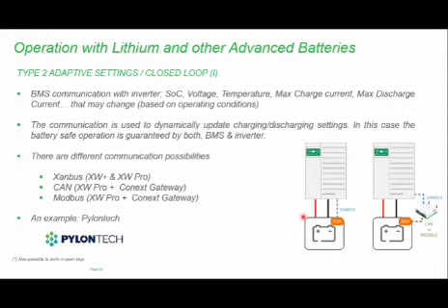So that's a key integration here. The real benefit of closed loop communication is that you're able to utilize the full extent of the batteries. In open loop, it's solely the BMS of the battery, if the battery even has a BMS, that handles the safety and proper utilization of the battery, like tripping a breaker if you're overcharging or over discharging it. In closed loop communication, because of this communication line, you have both the BMS of the battery and the inverter itself properly managing the battery for safety and full utilization.